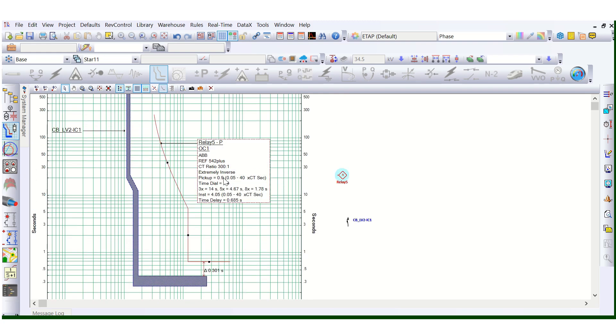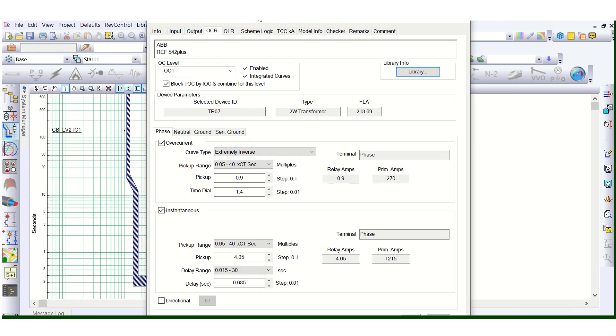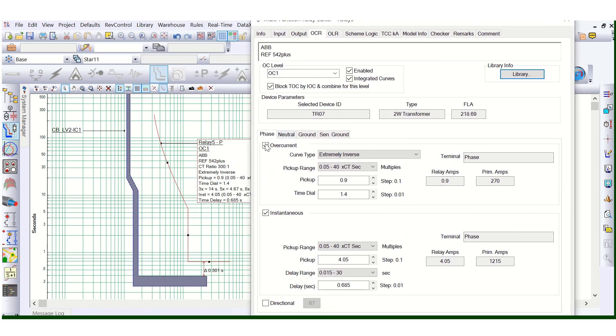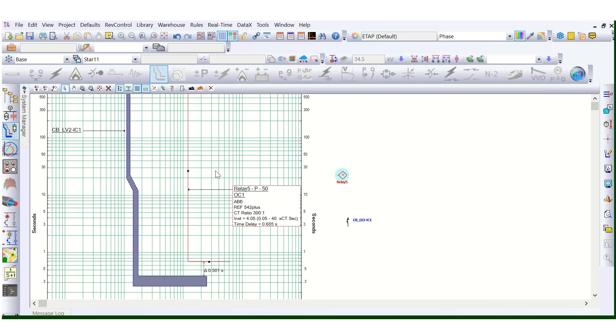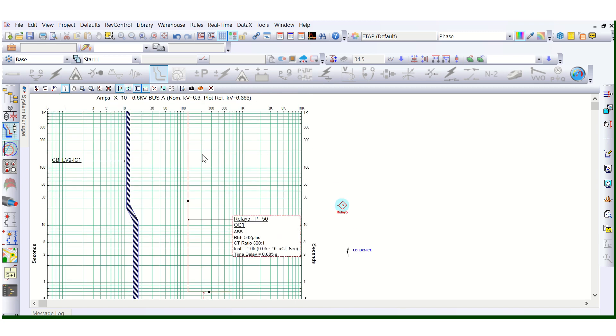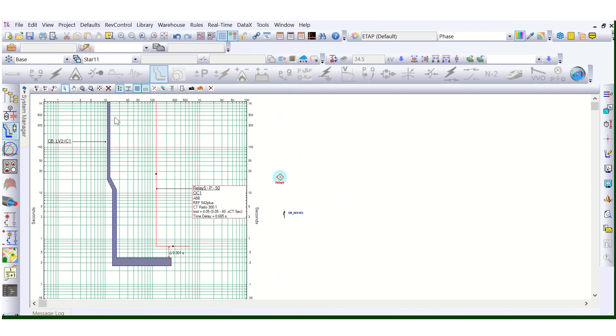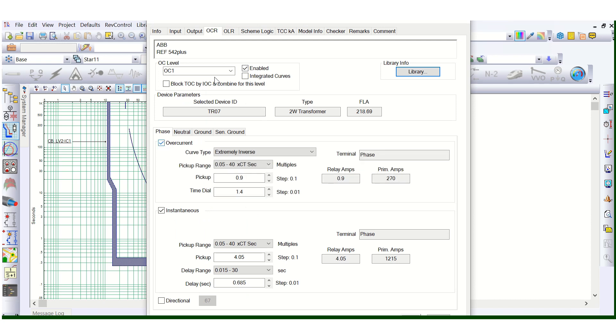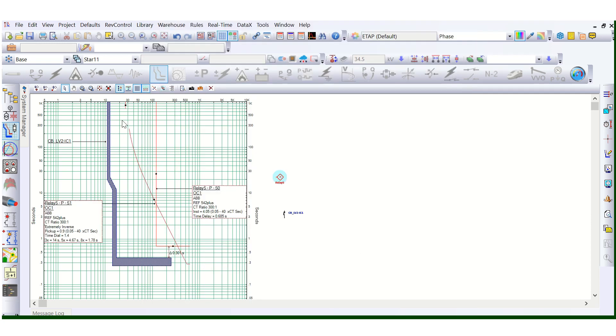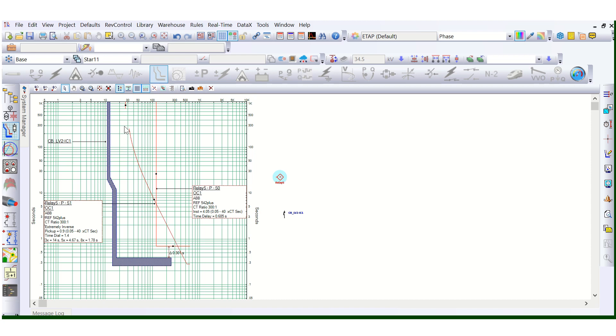If we disable 51 and keep only 50, we can see only this 50 curve. But what's the consequence? This part of the characteristic will not be protected — it is not coordinated. That's why we enable 51 IDMT for better protection.